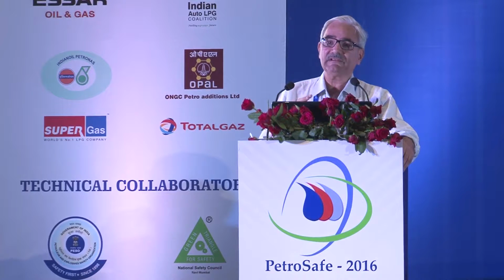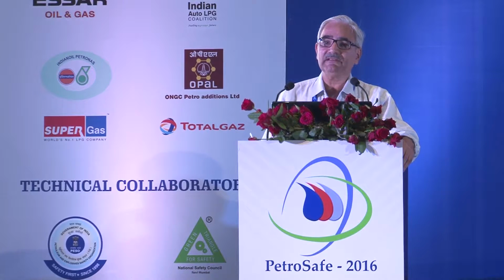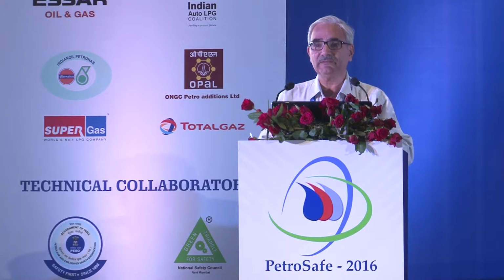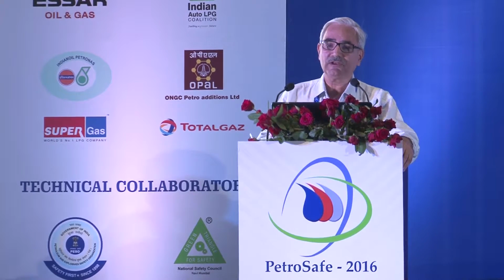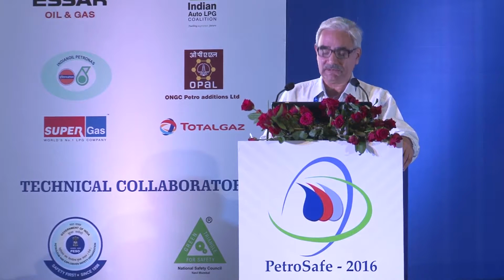For a pressure vessel in a pressurized condition, what is the limitation? The thickness of the vessel, normally we limit it up to 50 millimeters. Beyond that, if you go for a higher thickness vessel, it has its own issues. So the capacity is limited based on the total thickness; we are not going beyond 50 mm. If it goes beyond 50 mm, then more and more stringent requirements come into the picture.